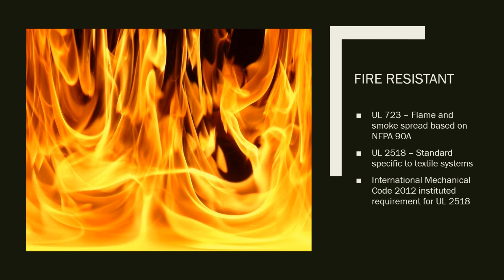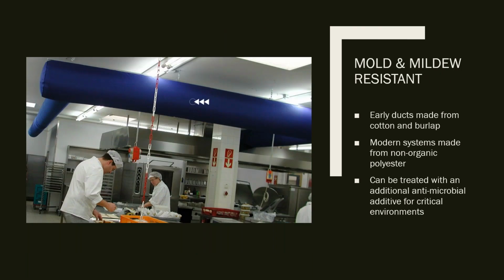With these standards, you're not going to have any type of fire hazard by using fabric ducts. And back in 2012, the International Mechanical Code began requiring compliance with UL 2518. So we are approved in building codes all across North America.